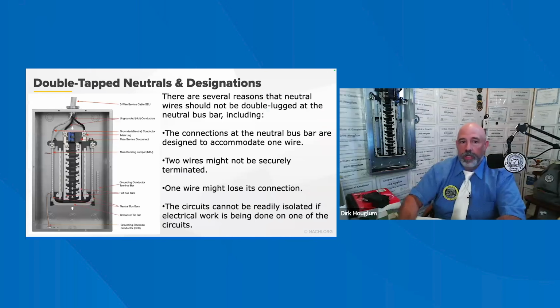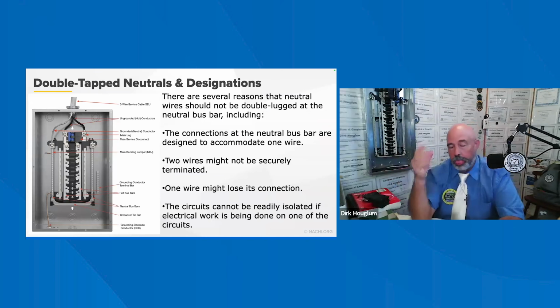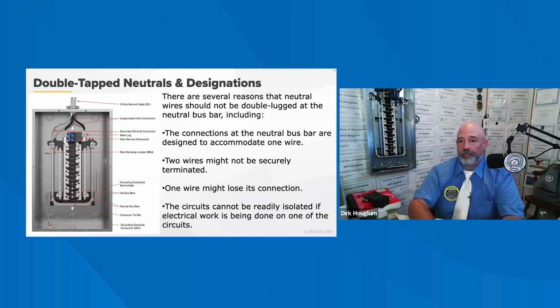So there you go. The grounded conductors, commonly called neutrals, are where our white wires are inside the residential electrical panel board. Only one neutral wire is permitted to be connected under a lug in a neutral bus bar. Refer to this illustration here. Panel board neutral bus bars are usually not listed for more than one wire per terminal, or fastener.